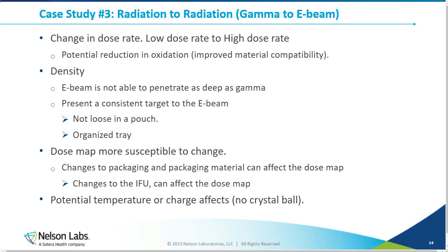So our next consideration is a change from radiation to radiation, but not just gamma to gamma. We're going to do a little bit more of an extreme change, such as gamma to E-beam. So this is a change in the dose rate. So gamma, again, it's a low dose rate. Generally, you're receiving the dose over the course of hours. Whereas for E-beam, again, it's over the course of minutes. That's a pretty big change in how much energy is being entered into the system at a time.